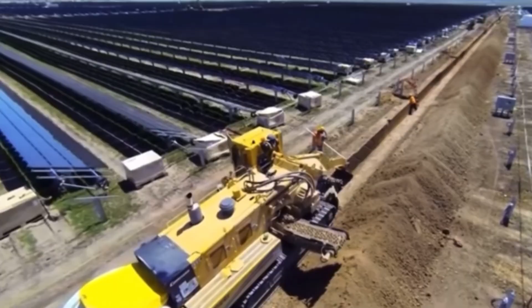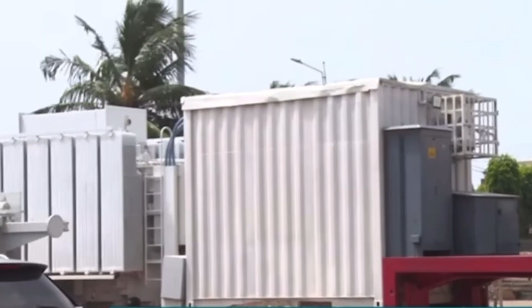Execution began in early April 2026, and the pace has been aggressive. Phase 1 of the program targeted 6 primary substations in Accra: Adenta, La Teshie-Nungua, Nmadzor, Batsona, and Lashibi. At each site, old transformers operating at 26 MVA were replaced with higher capacity units rated at 39 MVA, a significant jump that greatly improves the load handling capacity of each substation and reduces the risk of overloads triggering outages downstream. Phase 1 at the Nmadzor primary substation was completed successfully.